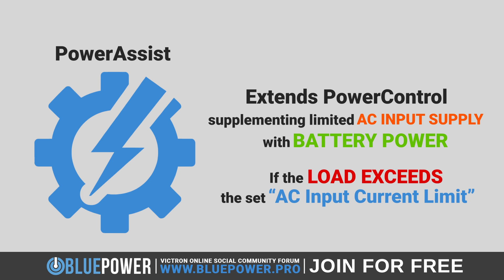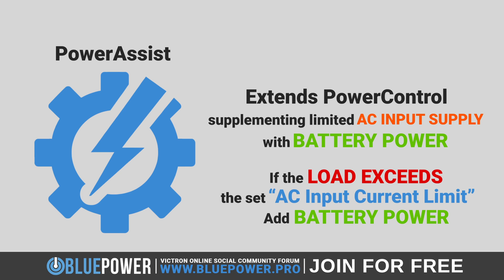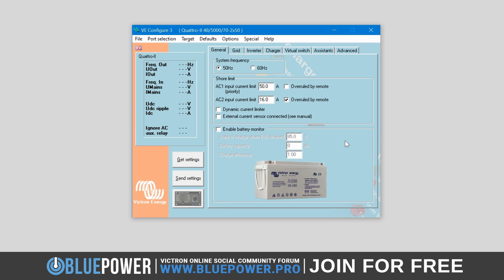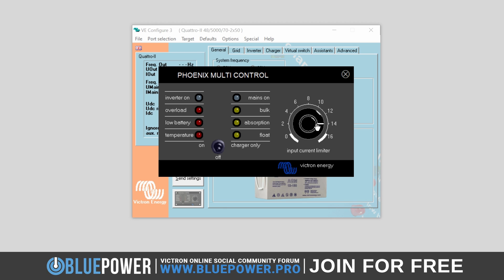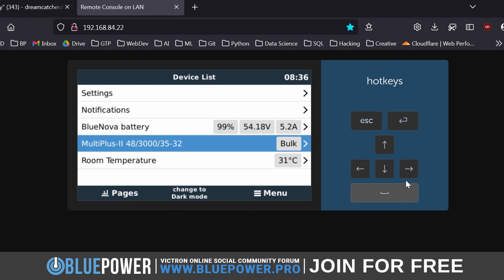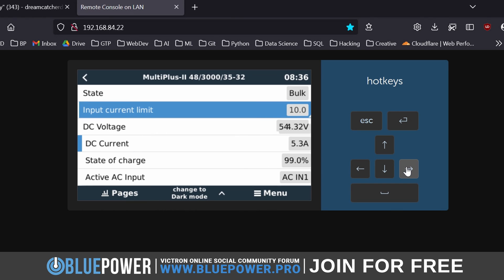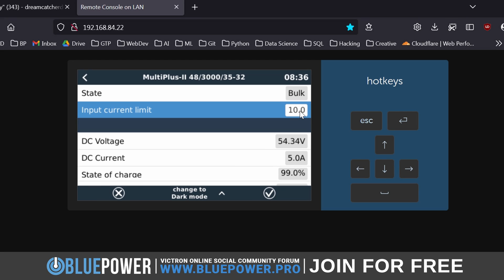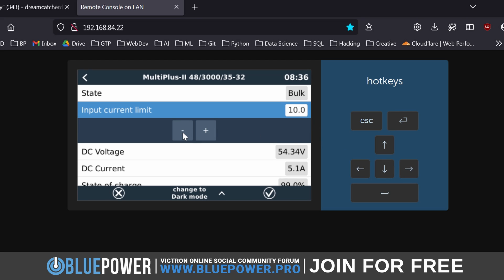The power assist feature extends power control functionality by supplementing a limited AC supply with battery power. If the load exceeds the set AC input current limit, the inverter charger will automatically add battery power to meet the demand without exceeding the AC source's limits. When 'overruled by remote' is checked, the setting can be overridden by an external control such as a remote panel or via the Cerbo GX interface — found by going into the inverter's menu, changing the input current limit using the plus and minus buttons, and pressing the check mark to confirm.